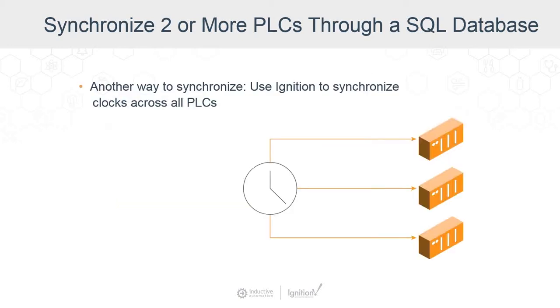Another common form of synchronization customers do with transaction groups is synchronizing clocks across all different PLCs. PLCs don't inherently communicate to time servers, so when switching between daylight saving and standard time, Ignition running on a machine can communicate to a time server and synchronize the time across all PLCs. Keeping those clocks synchronized — whether when values drift out of sync or on a continual basis — is another great use case. A transaction group is used for each PLC to synchronize the clock.